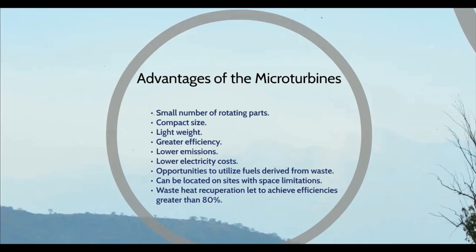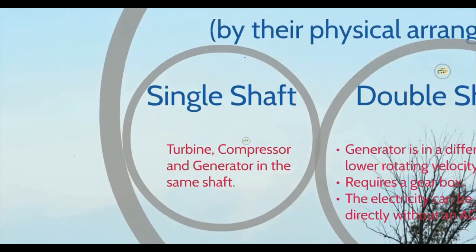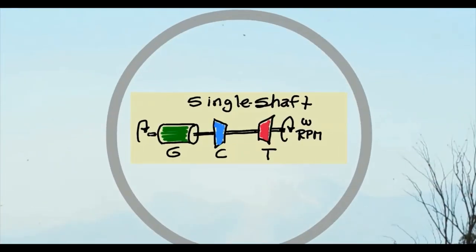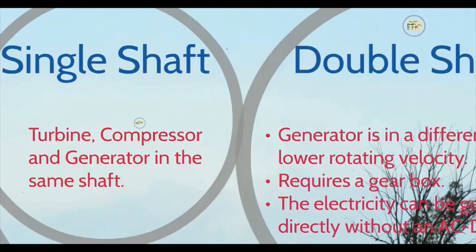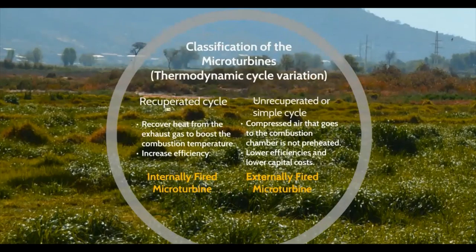Microturbines can be classified by the physical arrangement of their component parts. The first type is single shaft, where the turbine, compressor, and generator are on the same shaft. The second type is double or two shafts, where the generator is on another shaft, which doesn't require an inverter to change the frequency of the AC power generated, because of the low rotational velocity.